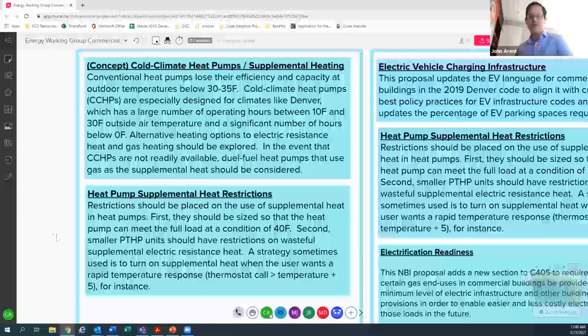So just for heat pumps, there are restrictions on the use of supplemental heat. Make sure they can meet the full load at whatever the rated condition is. And secondly, there are some of the smaller units, especially those used in small hotels or motels or residences, where the units have a control capability where if the set point temperature that the user specifies is much higher than the actual temperature, it may trigger the resistance heat during times when you wouldn't really need to run the resistance heat, but they want that big bump or boost in temperature. So it's worth considering restrictions on systems that have that kind of feature to use resistance heating when it's not that cold out.